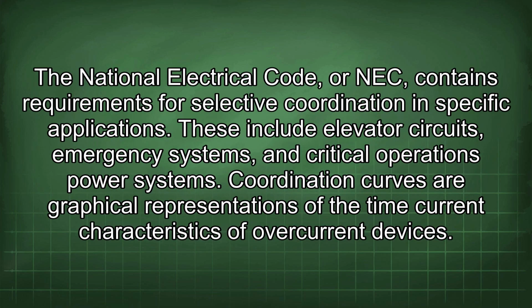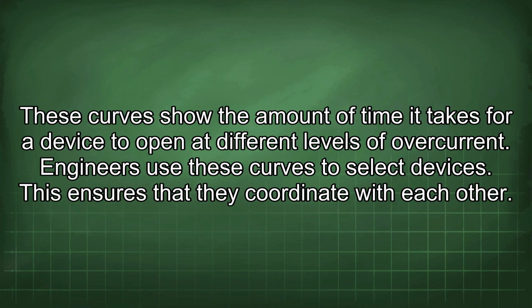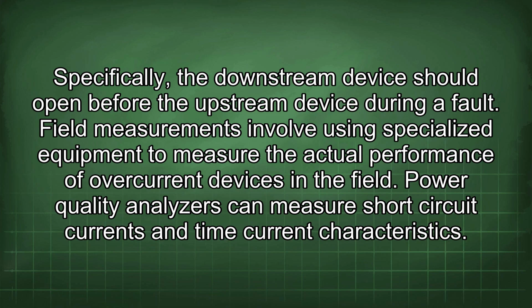The National Electrical Code, or NEC, contains requirements for selective coordination in specific applications. These include elevator circuits, emergency systems, and critical operations power systems. Coordination curves are graphical representations of the time current characteristics of overcurrent devices. These curves show the amount of time it takes for a device to open at different levels of overcurrent. Engineers use these curves to select devices. This ensures that they coordinate with each other. Specifically, the downstream device should open before the upstream device during a fault.